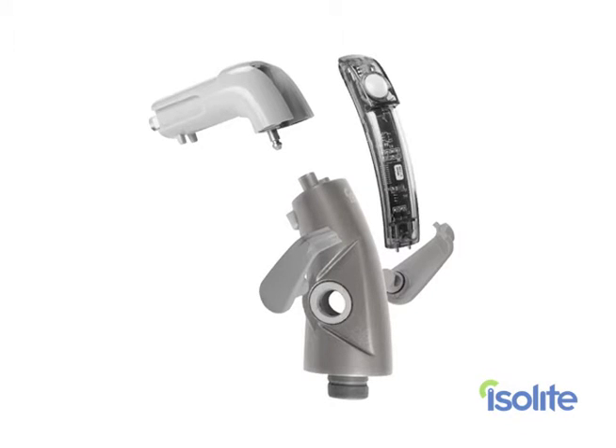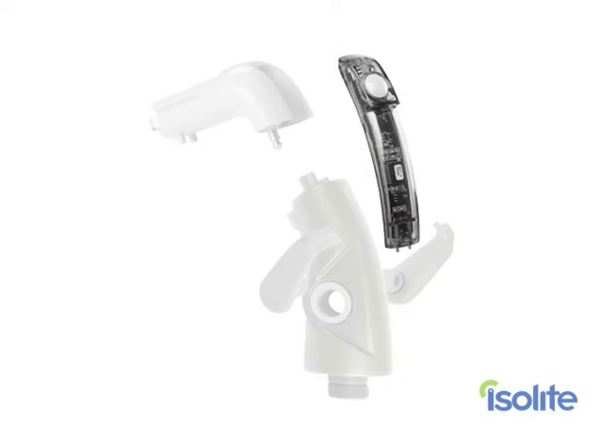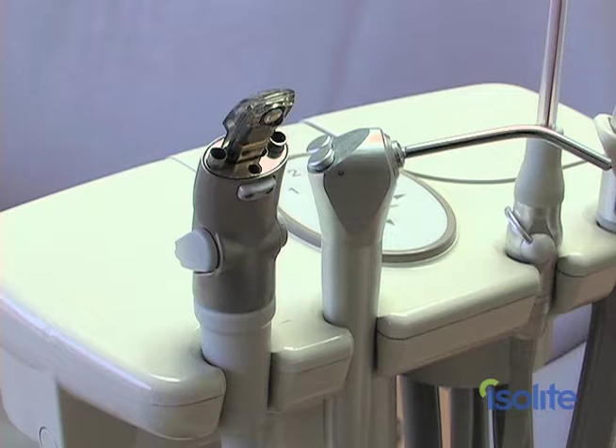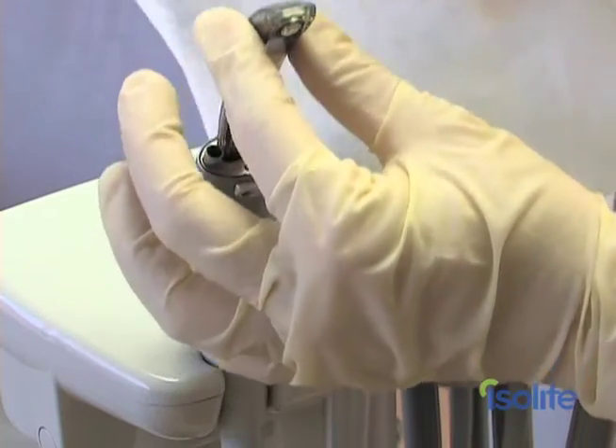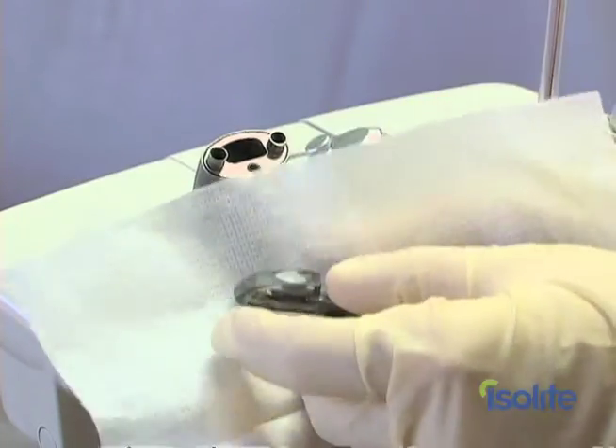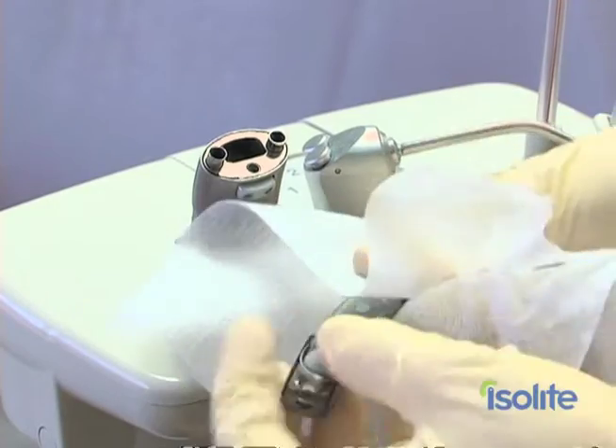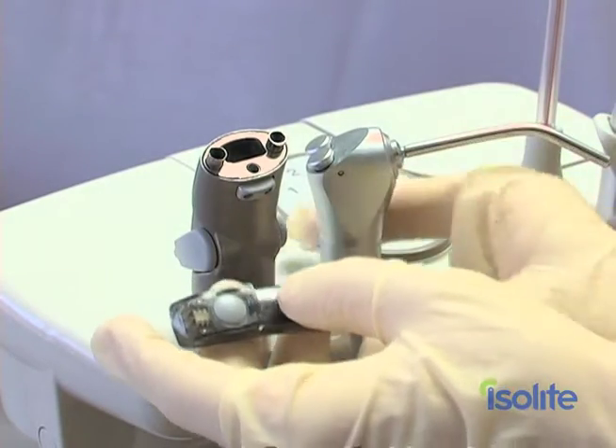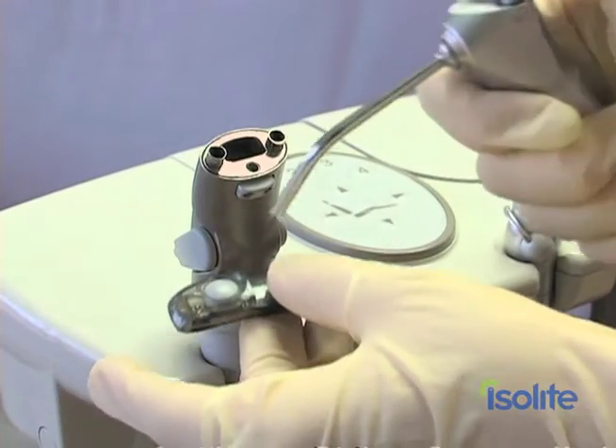If you have an Isolite dry-field illuminator, you will need to clean the LED smart stick. Of course, this is not necessary if you have an IsoDry system. The LED smart stick houses the LED light source and the computer circuitry for your Isolite system. This component requires additional special care and handling. Clean the LED smart stick by wiping it down with a surface disinfectant. Remember, wipe, never spray. Never submerge, autoclave, cold sterilize, or chemically sterilize this component.